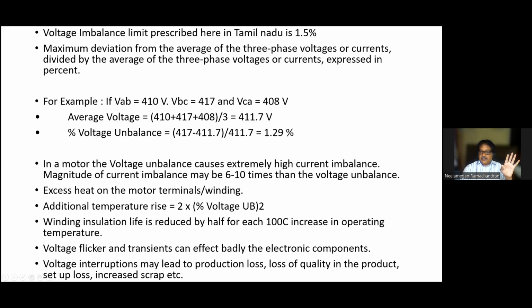And this voltage imbalance causes extremely high current magnitude, high current imbalance. So terminal overheating: we can always see a phase in the terminal box of a motor black in color, heating, and it will become brittle. Unnecessarily there won't be any problem, but unbalanced voltage is the culprit there. The problem of unbalanced voltage, to my knowledge, is mostly inside the factory itself, because single phase equipment is connected without any control. Electricians and electrical supervisors, everybody, connect single phase equipment in the DB, that is the distribution board, without any control. All grinders, bench grinders will be there, even single phase welding machines, cleaning vacuum, everything in single phase they connect in the DB.